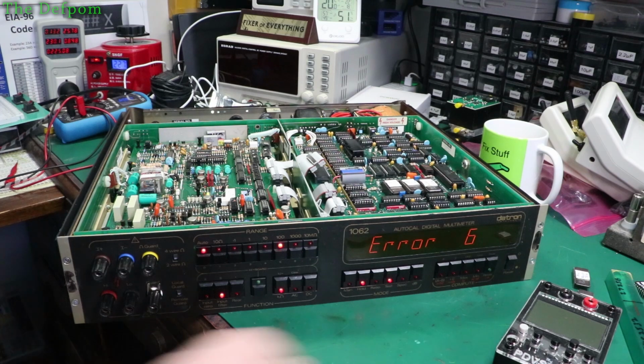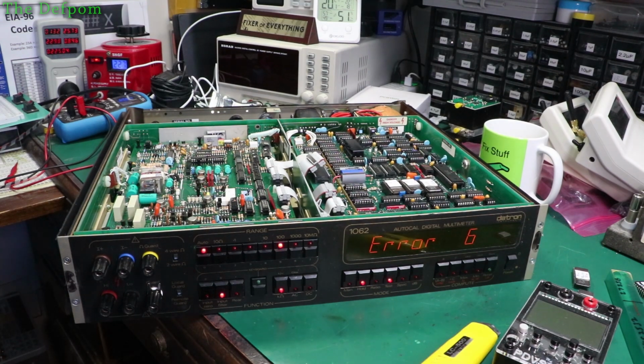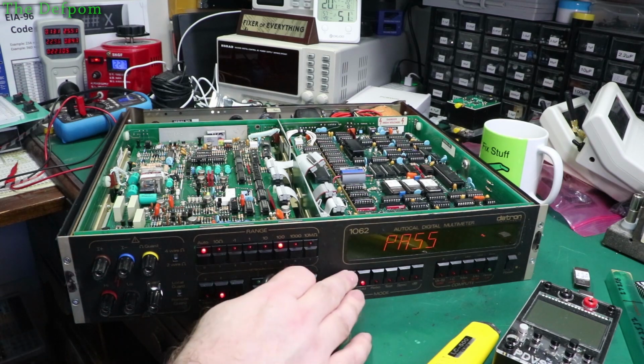Yep, okay, I'm going to look into that one. Maybe a calibration thing. It may be there's a slight difference in this firmware, which means it can't be used on this one. Alright, so error 6 is a resistance range error. So it reckons it's like a 10k test and it's failed resistance. So either there's an issue with the resistance range. I don't actually remember if there was one or not. I should probably put the original EPROMs back in again and retest that. But I thought I'd cleared all the errors on this thing. I thought I had. Anyway, and what's the next thing? AC passed as well, so that's fine.